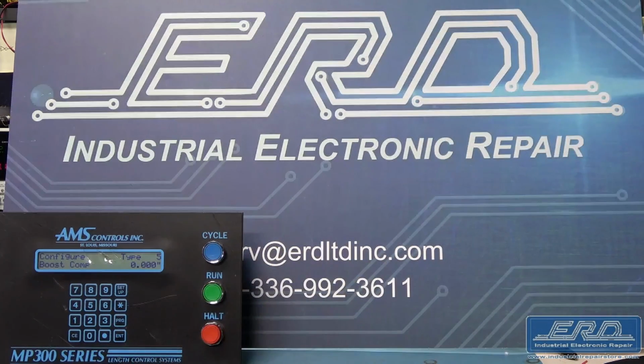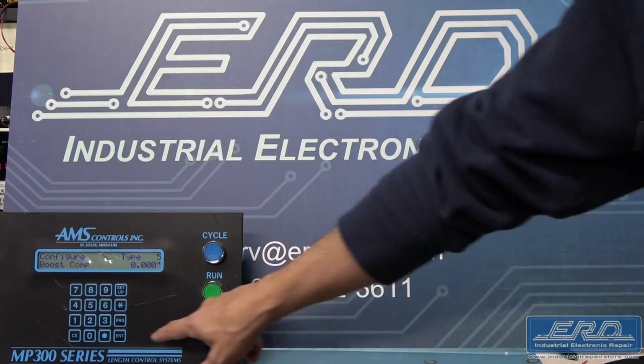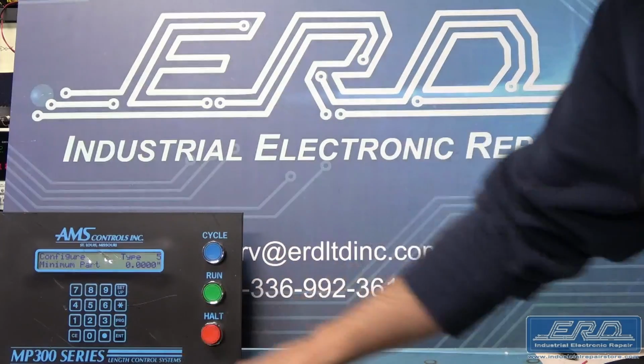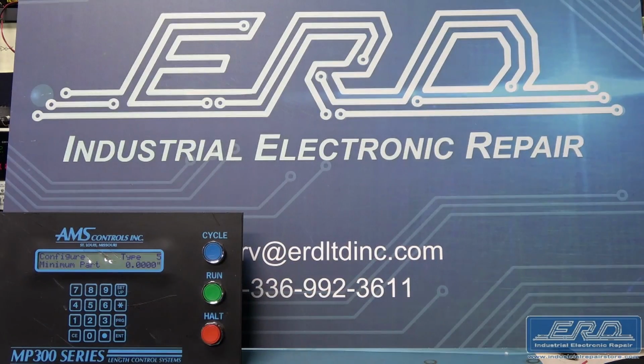We rebuilt the control board and replaced the battery, which allowed us to go through and program any of the menu settings. We also verified all the inputs and outputs and replaced the damaged input.